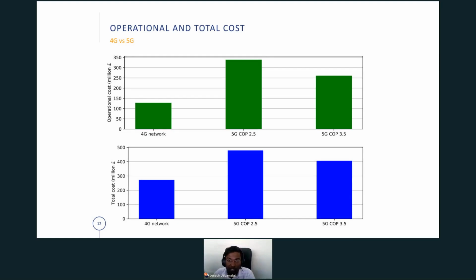If you compare the operational cost, the fourth generation operation cost is much lesser compared with the fifth generation networks. The reason is the COP is higher, and we can get cheaper electricity using a private wire for the centralized heat pumps. But for the fifth generation distributed heat pumps, we still require electricity from the grid, and that cost is much higher. So comparing the total cost, the fifth generation system cost will be much higher compared with the fourth generation systems.